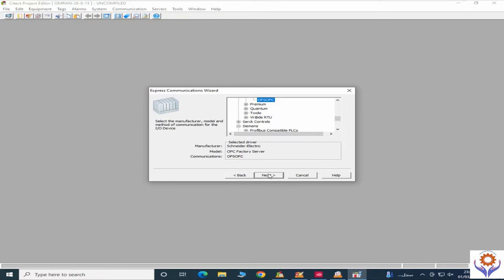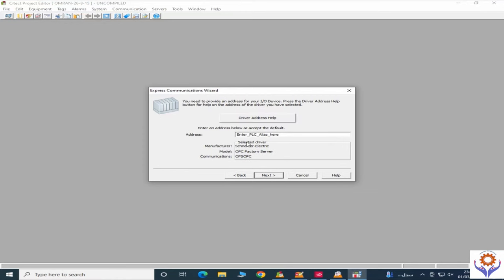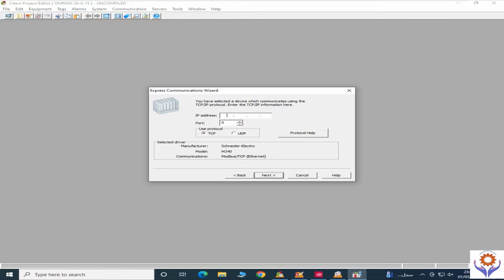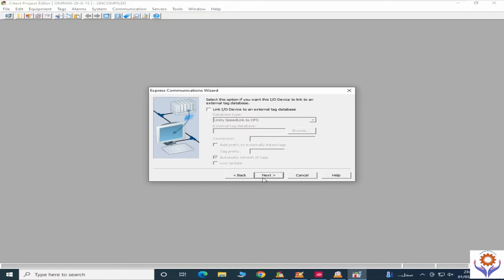And if you give next, it will ask you, this is OPC, yeah? So I will give an example, M340 PLC example. I will give TCP IP. If I select it, it will ask you the IP address. You enter the IP address, for example 192.168.0.1, and you have to give the port 502. And it will ask you TCP or UDP.